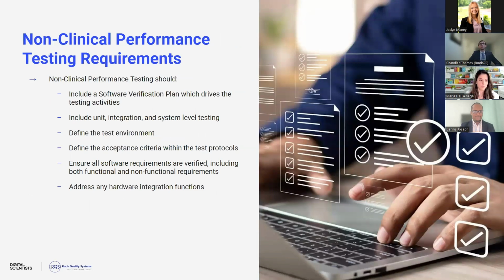So for non-clinical performance testing requirements, again, this is something that you can get a head start by looking at the predicate devices and what sort of performance testing that they performed. But it will always include a software verification plan, which drives the testing activities that acts as essentially a catalog of your test cases, describing the test environment, and also addressing the unit, integration, and system level testing that you'll perform in order to verify and validate your device.